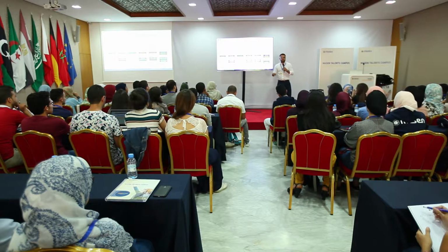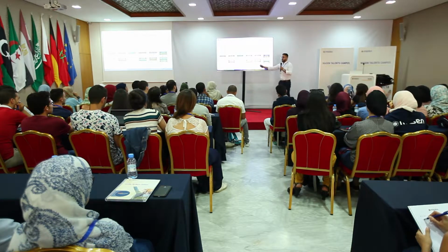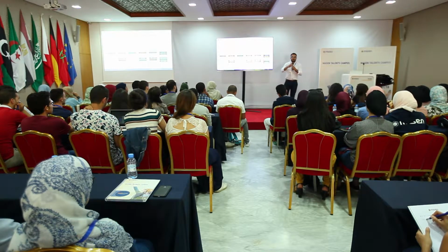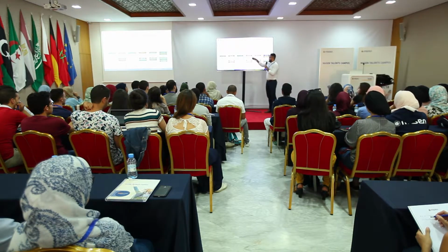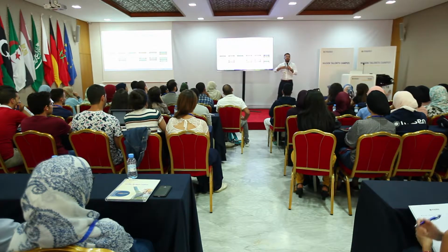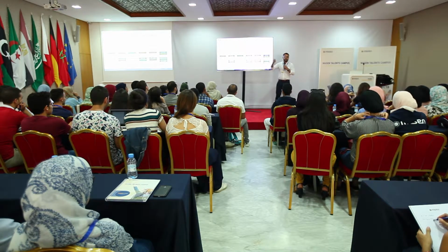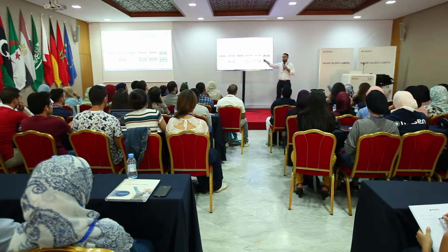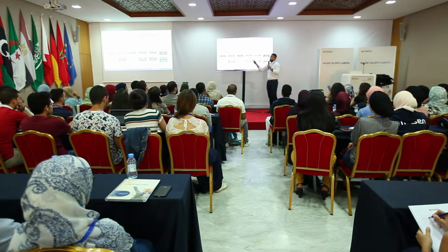Another technical factor is the capacity factor. Depending on what you design the system for, you might be required to meet a specific capacity factor. I mentioned this before, but I didn't really explain what it was. The capacity factor is a quantity that measures how available my system, my plant, is throughout the year. It's basically the ratio between the yield divided by the potential yield, the theoretical maximum, if I was operating at all times at the maximum capacity. Right?